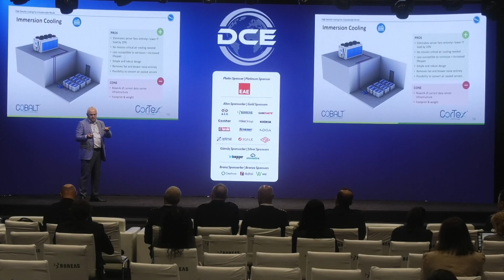Now there's another metric to take into consideration. For the last 25 years, everyone's been talking about PUE, power usage effectiveness. But right now the industry has discovered it's a false metric. Why? Because 20% of energy consumption is wasted by the fans, and that's considered IT load.